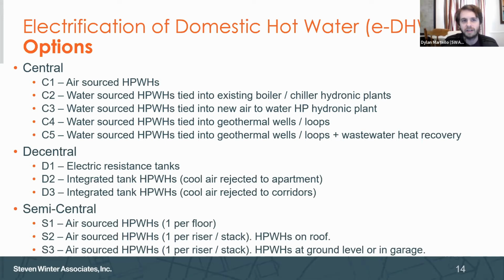Now, some of our other options, and this is where things can get very creative, are on the water source side. In an existing building, this is where I think this could potentially play a huge role. If an existing building has a boiler plant and chiller plant that's producing hot and cold water for a hydronic system and hydronic space heating, we have the ability to tie water source heat pump water heaters into that existing hydronic loop and steal heat from that. Of course, that would need to be coupled with adequate due diligence, making sure that we're not eating into too much of the capacity of the system, and because we are stealing heat from that hydronic loop, we want to make sure that the space heating needs for the building would still be met. But it does have the ability to provide some heat recovery in the summer and reject cold water back into the hydronic loop, and as a result, utilize some free cooling potential just to make our hot water for the building.